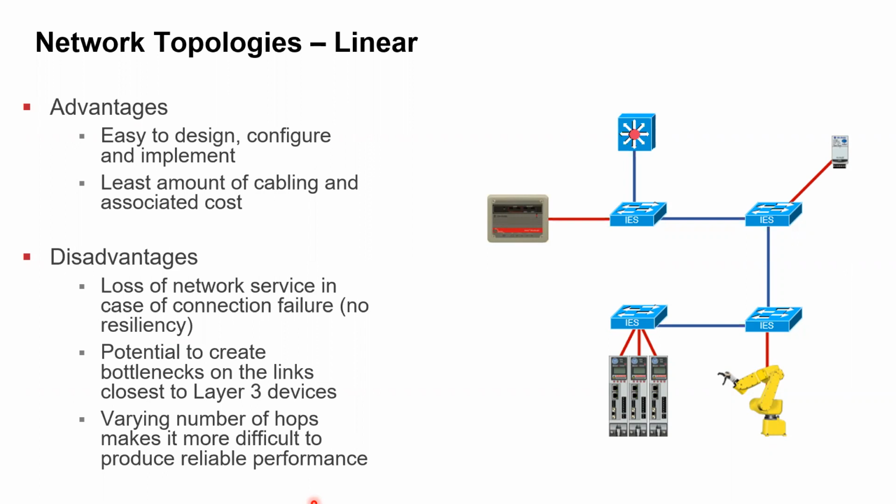The advantage of this is, hey, it is pretty easy, right? Probably a limited amount of cabling. But the biggest disadvantage of this is that if there was any kind of break in the network along the way, like if we had a break in the network here, or if this switch here died, well, everything downstream is obviously gone and no longer visible to the controller. So it does work. We do see this network, but there are some inherent risks and disadvantages of that linear topology.